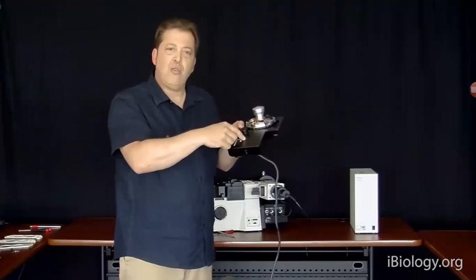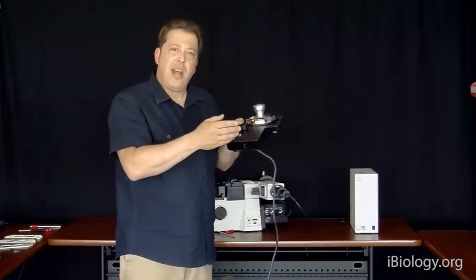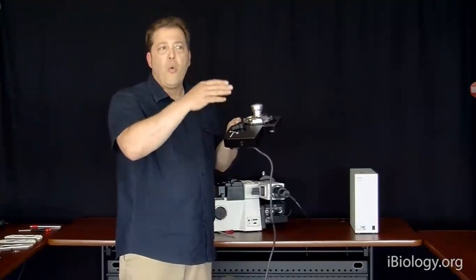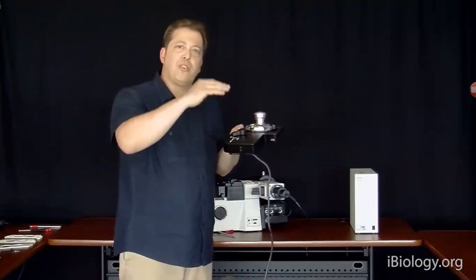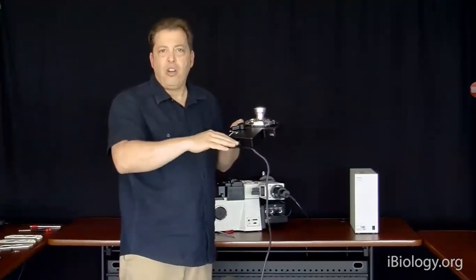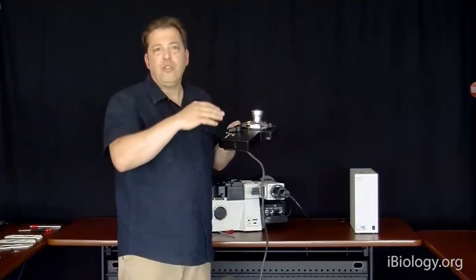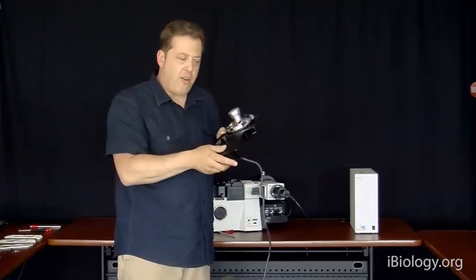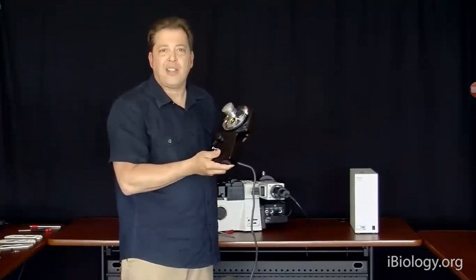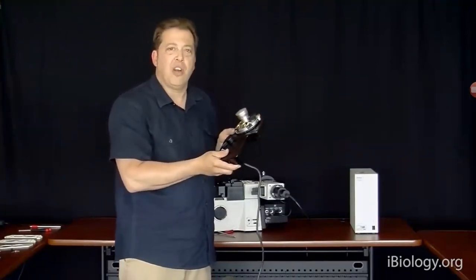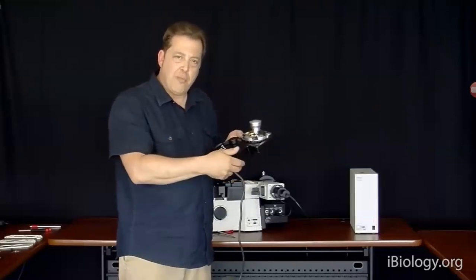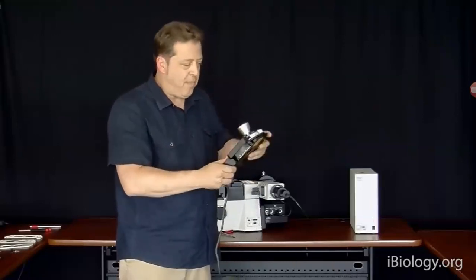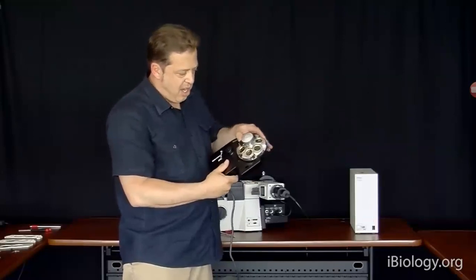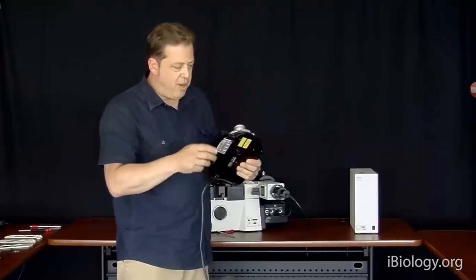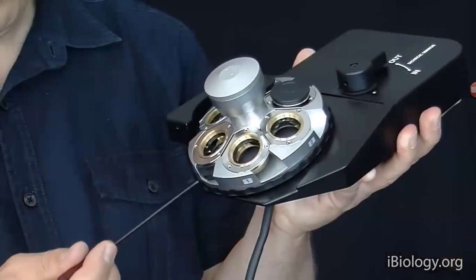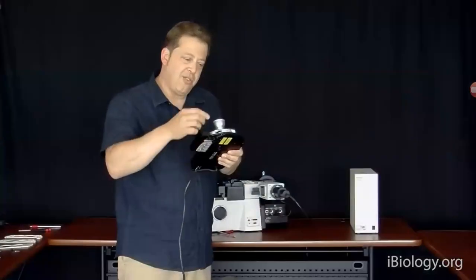and goes to a linear CCD array that actually knows whether the scope is in focus, whether it's drifting below due to gravity, or whether it's drifting upwards due to thermal expansion of the materials, and it tracks that, and it does it every 5 milliseconds. So it's imperceptible to the user, but it'll hold focus indefinitely. And basically, that's all there is really to this component. It's got slots here for your prisms for differential interference contrast.